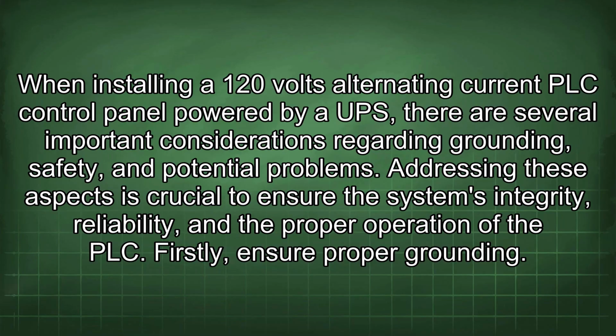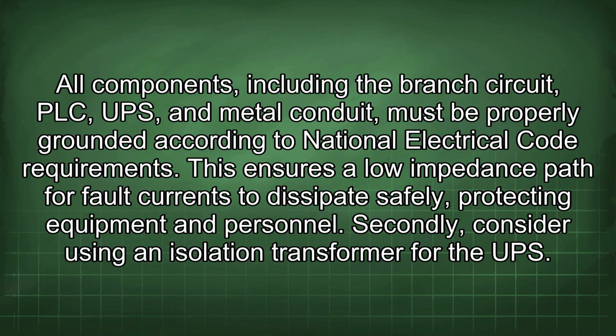When installing a 120 volts alternating current PLC control panel powered by a UPS, there are several important considerations regarding grounding, safety, and potential problems. Addressing these aspects is crucial to ensure the system's integrity, reliability, and the proper operation of the PLC. Firstly, ensure proper grounding. All components, including the branch circuit, PLC, UPS, and metal conduit, must be properly grounded according to National Electrical Code requirements. This ensures a low impedance path for fault currents to dissipate safely, protecting equipment and personnel.